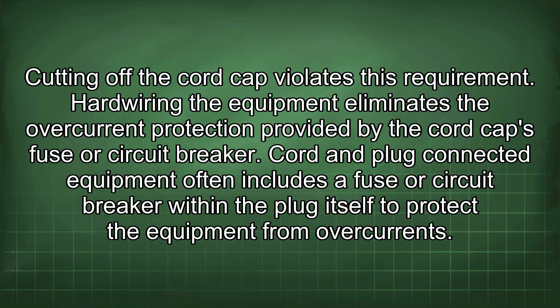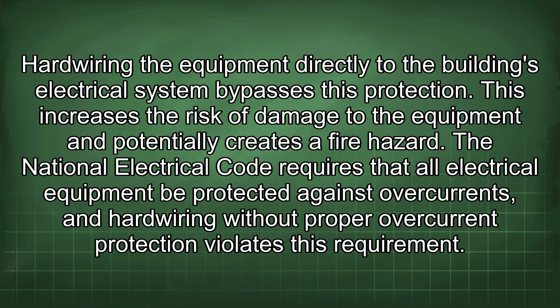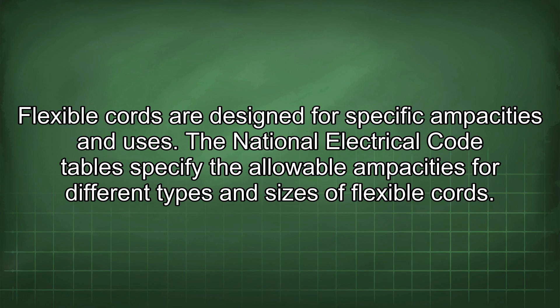The National Electrical Code requires that all electrical equipment be protected against overcurrents, and hardwiring without proper overcurrent protection violates this requirement. Flexible cords are designed for specific ampacities and uses. The National Electrical Code tables specify the allowable ampacities for different types and sizes of flexible cords. Using a flexible cord for a permanent connection, especially if it is not properly sized for the load or subjected to excessive strain or physical damage, can create a fire hazard.